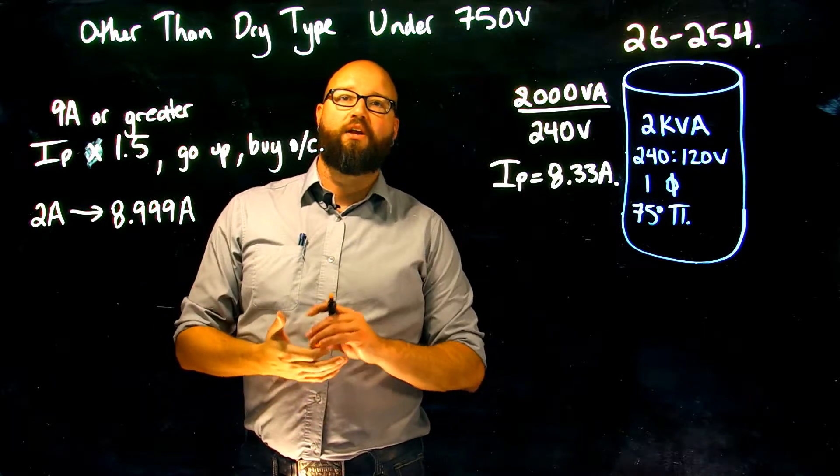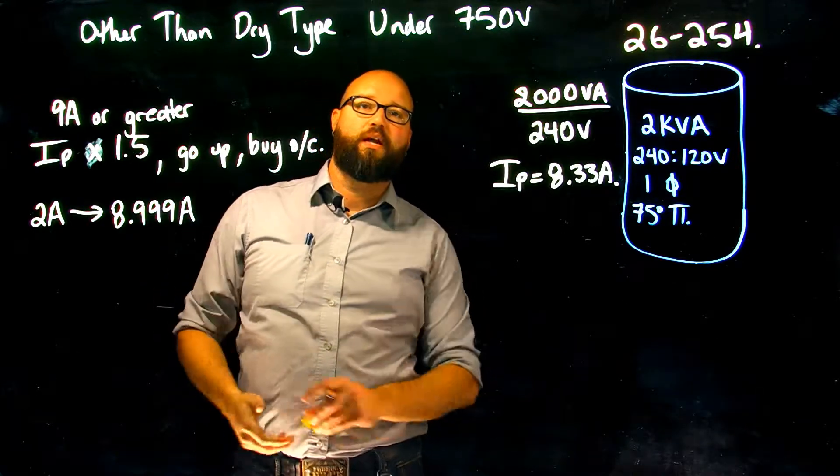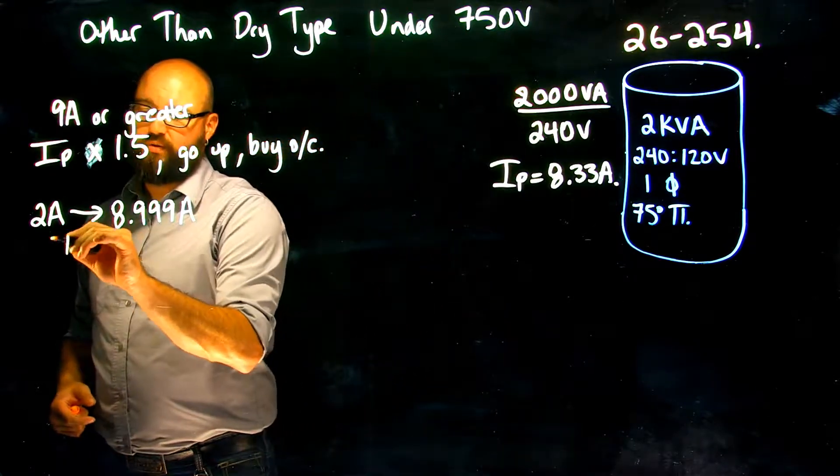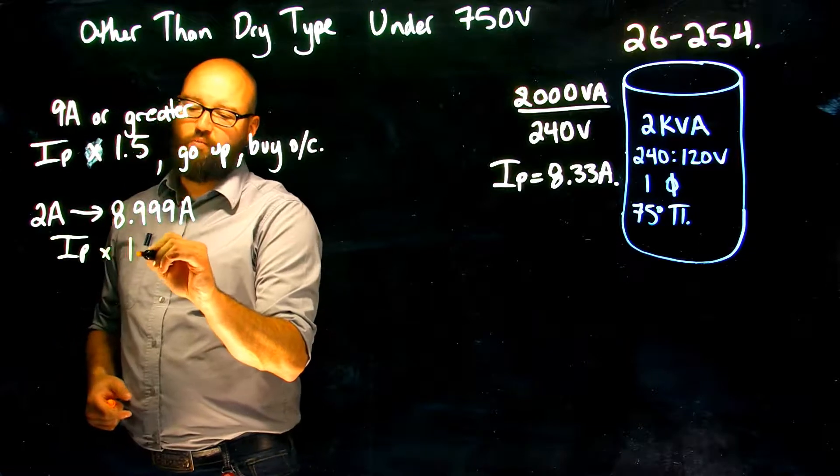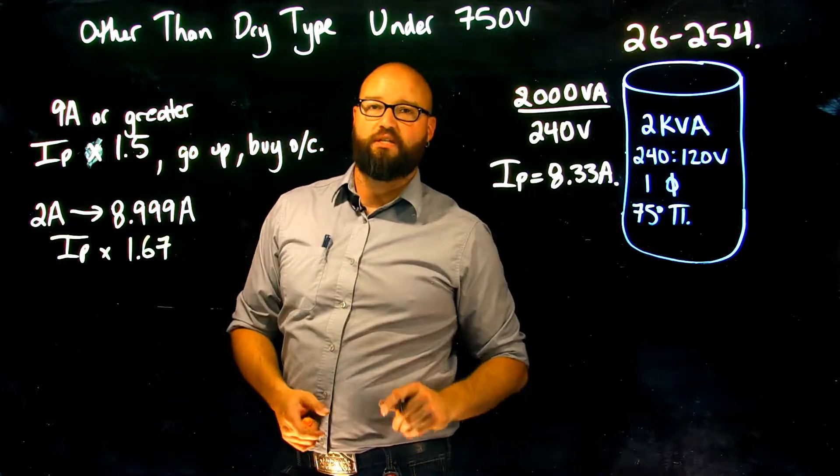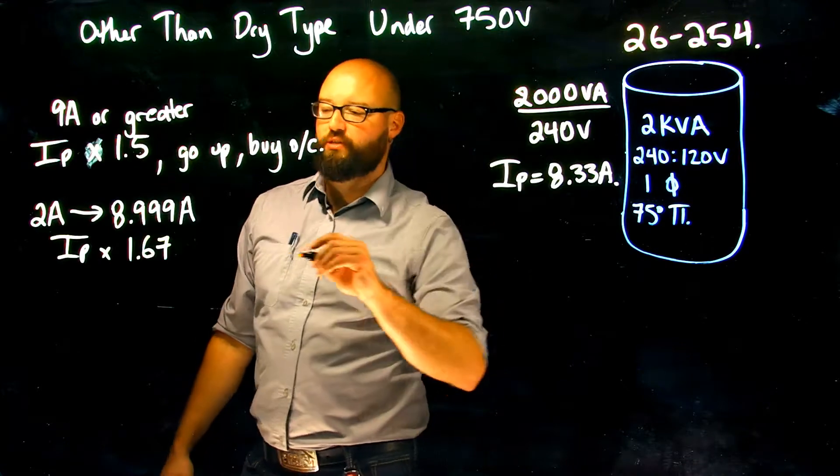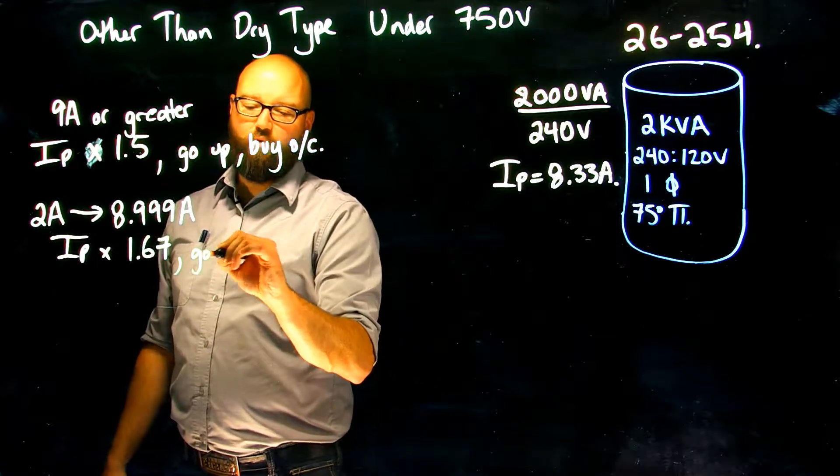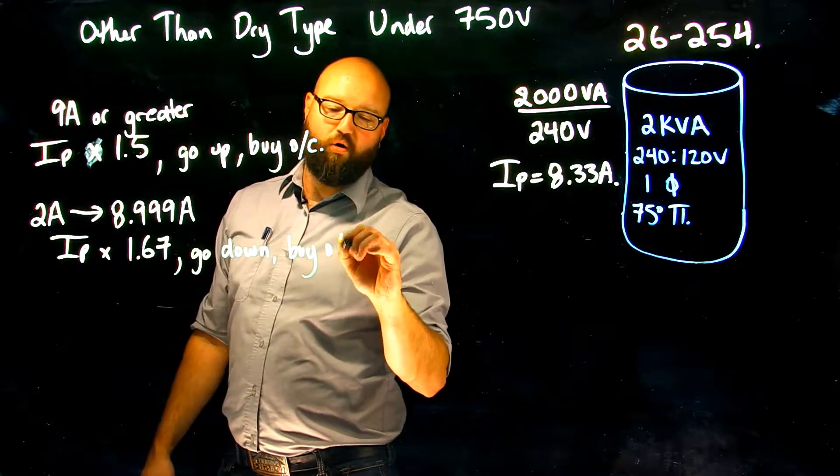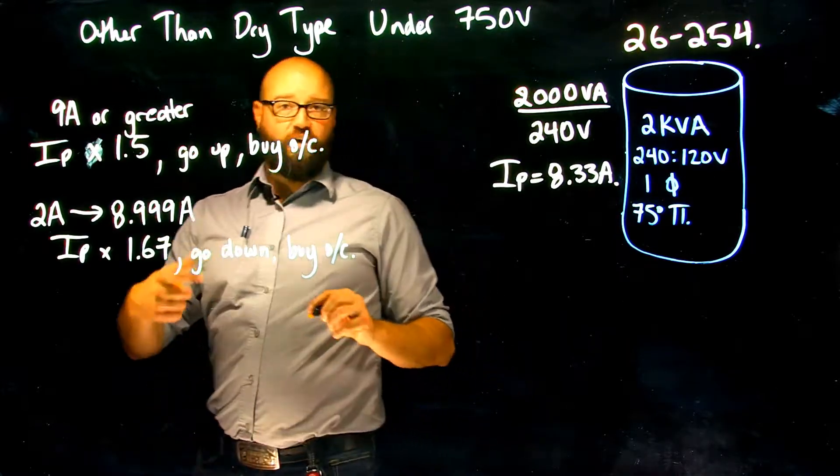So what we would do in this case, we would take our I primary times 1.67, and there are no exceptions to this. It doesn't tell me I'm allowed to go up to the next available size, so we would go down and then we would buy our overcurrent based on that number.